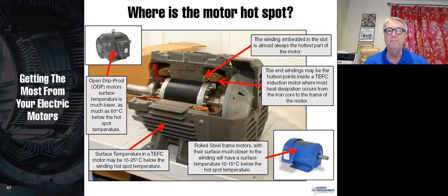Now, this is a totally enclosed fan cooled motor, and you can see that the air doesn't actually go through the motor. The air goes over the outside of the motor. So it comes in through the end bell here. It hits this fan, which is on the shaft of the motor. That fan is a centrifugal fan, which forces the air towards the outside, and then it goes over the outside, and you can see these fins molded into the cast iron that helps the cooling of that motor.